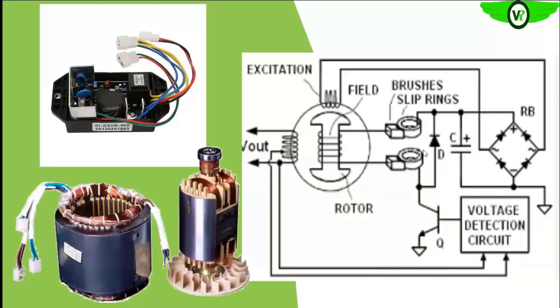AVR to the slip rings of your main field. This is the main field. These are the slip rings, 2 of the slip rings, and these are the representation of the 2 slip rings, okay? So they are fed directly from the AVR, and these are the 2 wires that go straight from the AVR to the generator main field.